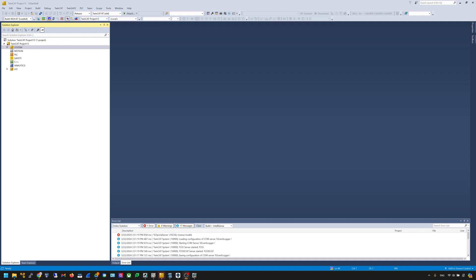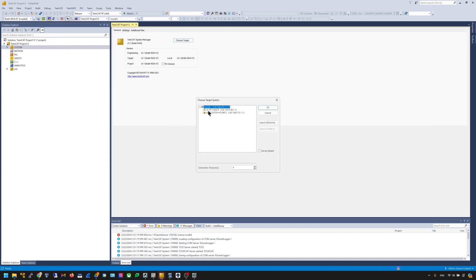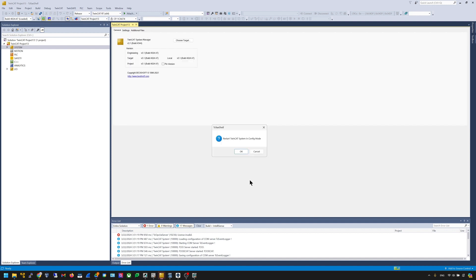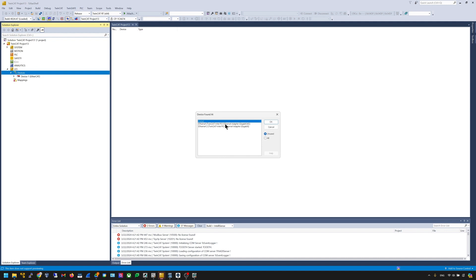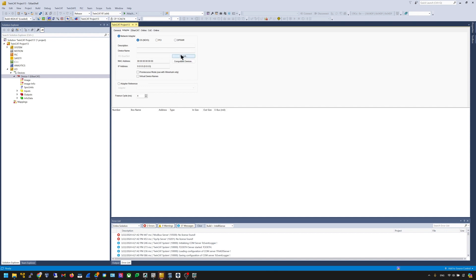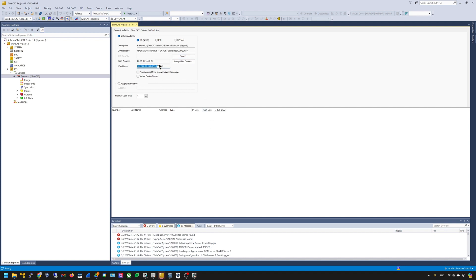Now we open the TwinCAT project and start configuring the TwinCAT side. First, make sure your TwinCAT editor is connected to the IPC you want to configure. Go to System, then choose Target — in this case I'm using this PC. Then go to Config Mode. This will take a moment to switch from Run mode to Config mode. Then we can add the EtherCAT master by going to IO Devices, right-click, New Item, choose EtherCAT master, and select the network interface you want to use.